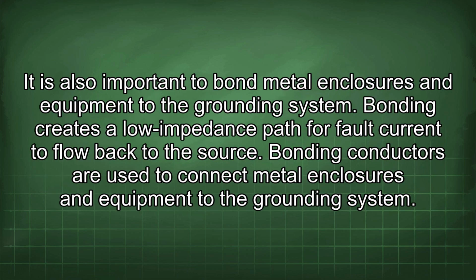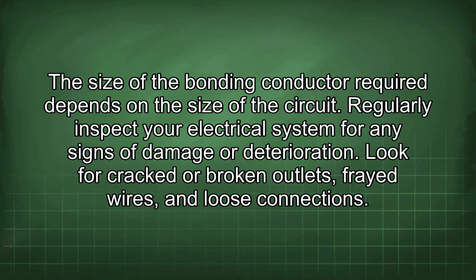It is also important to bond metal enclosures and equipment to the grounding system. Bonding creates a low impedance path for fault current to flow back to the source. Bonding conductors are used to connect metal enclosures and equipment to the grounding system. The size of the bonding conductor required depends on the size of the circuit.